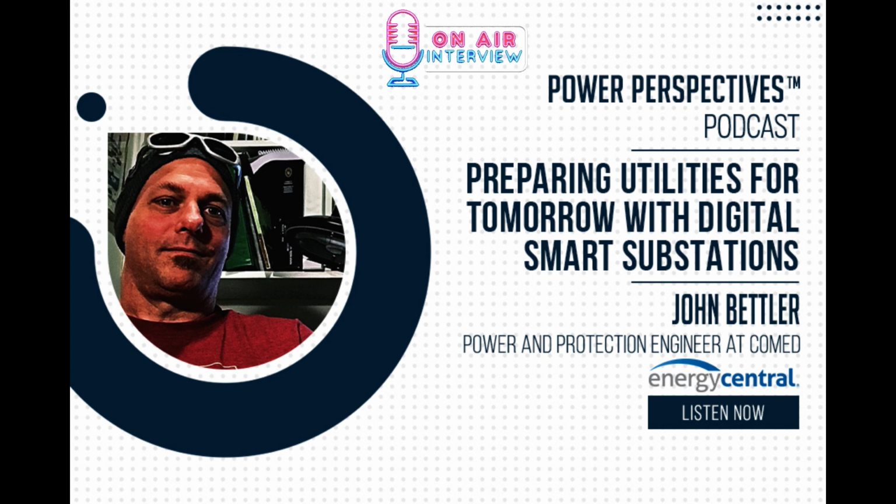I guess the one aspect too, when I talk about the fiber and the network, is a DSS would be IP communications for all your relays. Your bread and butter substation either didn't have communication or just had contacts or it was serial, but in a new DSS, you're going to be using IP communication to all your relays. So you'll have them on a network.